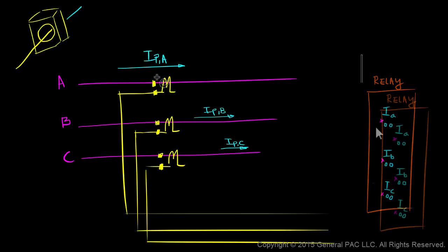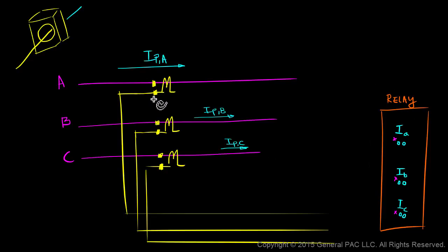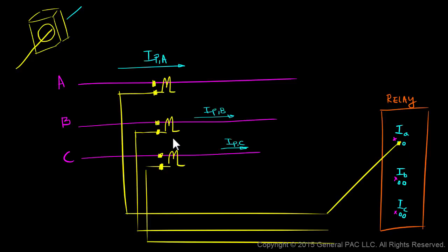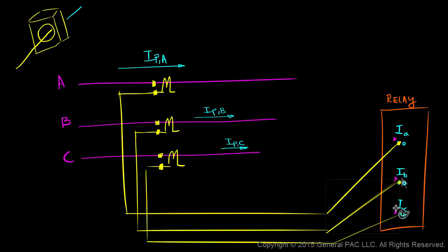The polarity side of our phase A CT, which is this lead here, should be connected to the polarity input terminal of our relay. Similarly, we'll have the polarity side of our phase B CT connected to the polarity input terminal in our relay. And lastly, we'll do the same thing for phase C.